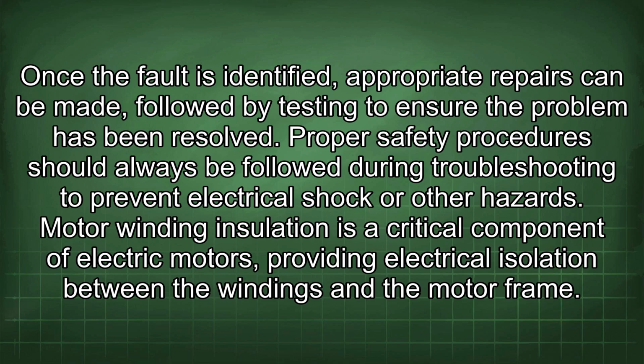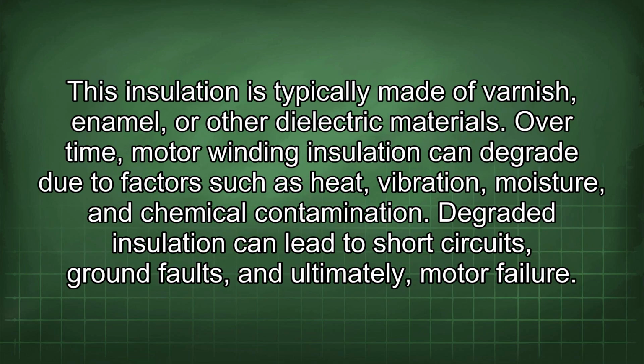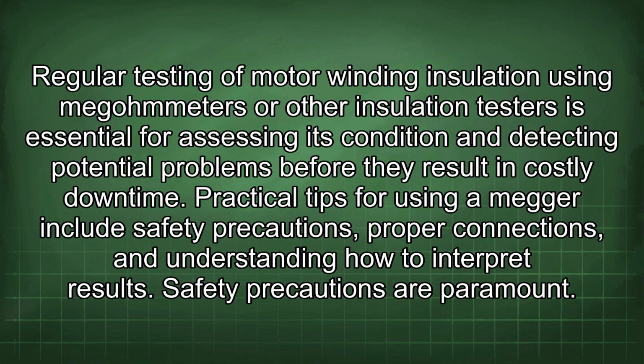Motor winding insulation is a critical component of electric motors, providing electrical isolation between the windings and the motor frame. This insulation is typically made of varnish, enamel, or other dielectric materials. Over time, motor winding insulation can degrade due to factors such as heat, vibration, moisture, and chemical contamination. Degraded insulation can lead to short circuits, ground faults, and ultimately, motor failure. Regular testing of motor winding insulation using megohmmeters or other insulation testers is essential for assessing its condition and detecting potential problems before they result in costly downtime.